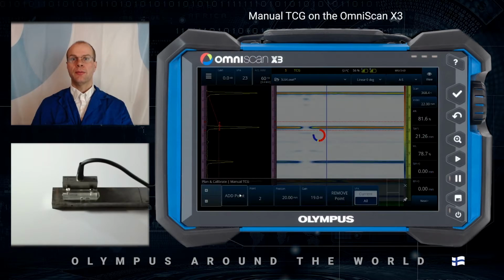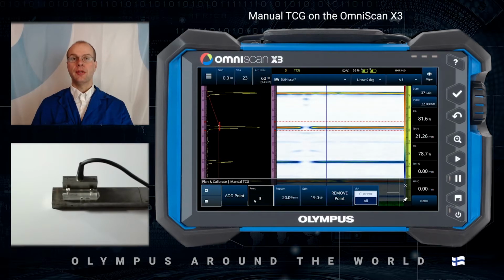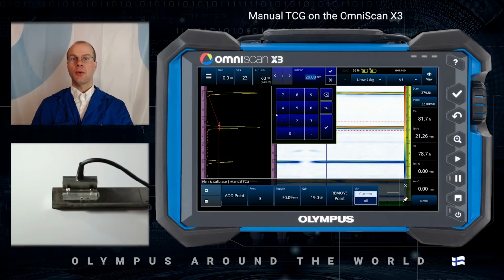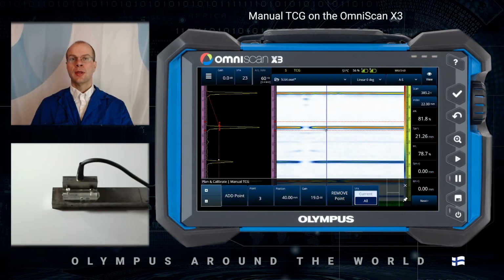I will add another point, which will be my point number three. I will change the position to the repeat back wall, so 40 millimeters. Now, instead of manually adjusting the gain, I will use the auto 80% function from the instrument. To do that, first, I will move the gate to measure the second back wall, or the repeat.